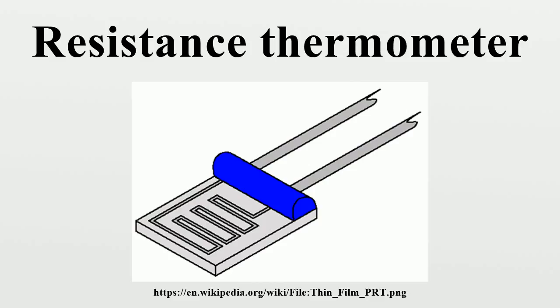Sources of error. The common error sources of a PRT are interchangeability, the closeness of agreement between the specific PRT's resistance versus temperature relationship and a predefined resistance versus temperature relationship, commonly defined by IEC 60751. Insulation resistance. Error caused by the inability to measure the actual resistance of the element. Current leaks into or out of the circuit through the sheath between the element leads, or the elements.